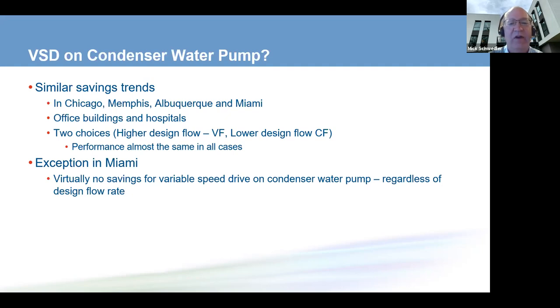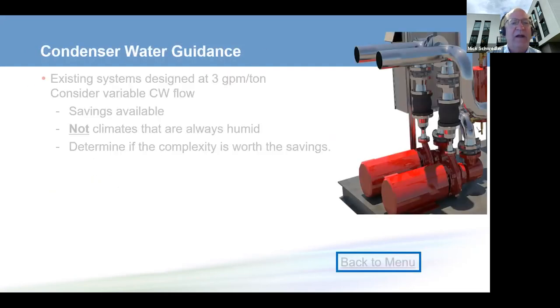So if you do any design in a climate like that, there aren't savings available. So from guidance, on existing systems, if people want to reduce their chilled water plant kW per ton and increase their efficiency, there's some savings available. It's complex, but it is available. People have done it in the past.